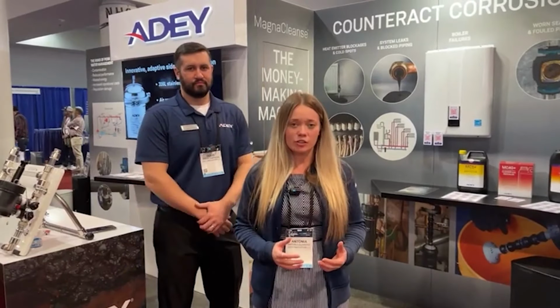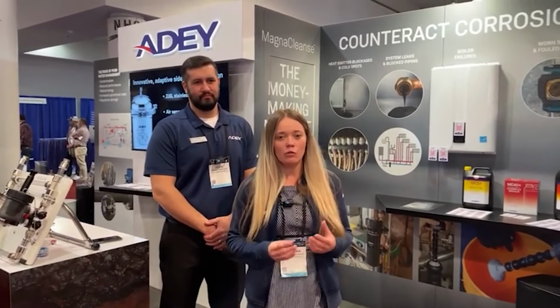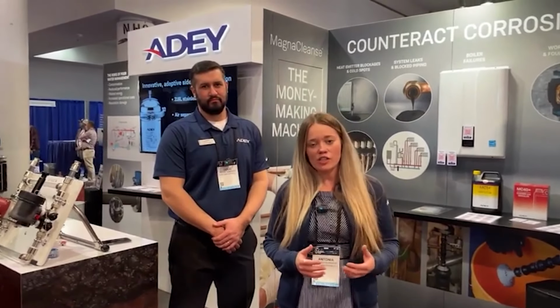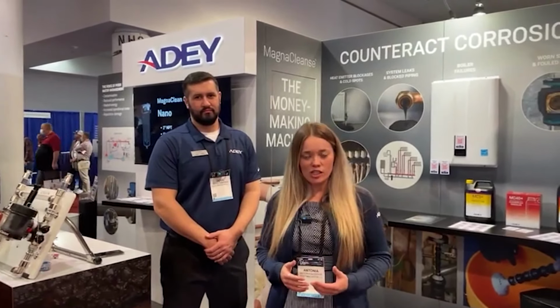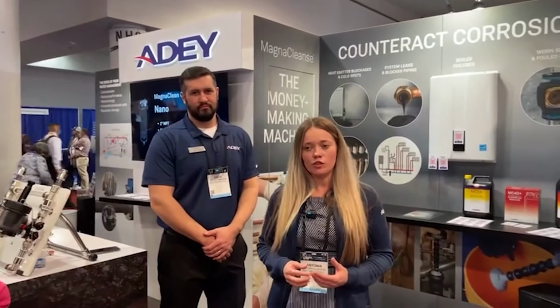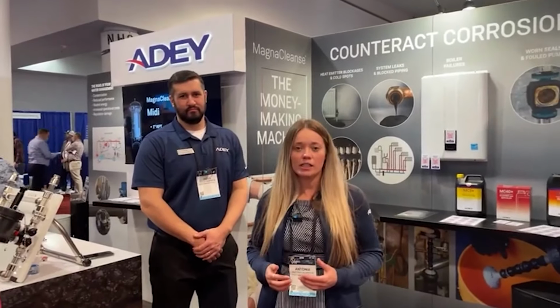So we manufacture a range of products for testing, cleaning, and protecting boiler systems, chilled water systems, and steam systems from corrosion. Corrosion occurs as contaminants and air get into the system. That then oxidizes and it causes magnetic particles to form in the system, also known as magnetite. What this does is it attaches to system pipework, heat exchangers, ECMs, causes them to block, overwork and crack. Eventually it can lead to boiler failures.